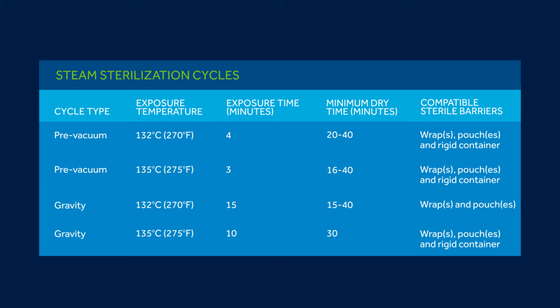It is the responsibility of the user to select the appropriate sterile barrier and process indicators for each sterilization cycle. Warning: generators and battery insertion guides cannot be sterilized with rigid containers using a steam sterilization cycle of gravity 132 degrees Celsius. Note: the generator and battery insertion guide have been tested to allow exposure to temperatures up to 135 degrees Celsius for 18 minutes in order to allow for variations in local requirements and regulations for sterilization protocols.